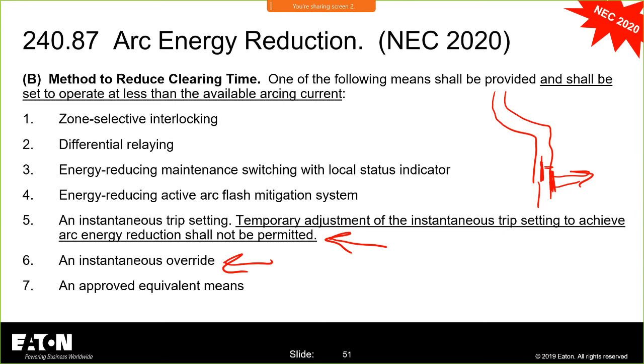And now here's an important thing that they did. They wanted to clarify, because there were a few people going across the country saying, oh, by the way, you can just roll down instantaneous and meet the requirements of 240.87 and roll it back up again. That is a no-no. For 70E purposes, you can't be changing set points in the field like that. If you roll it down, you don't know where you rolled it back to. And sometimes all of these trip units are different in what they look like. So they added this language right here that says, temporary adjustment of the instantaneous trip setting to achieve arc energy reduction shall not be permitted. You set it and forget it.